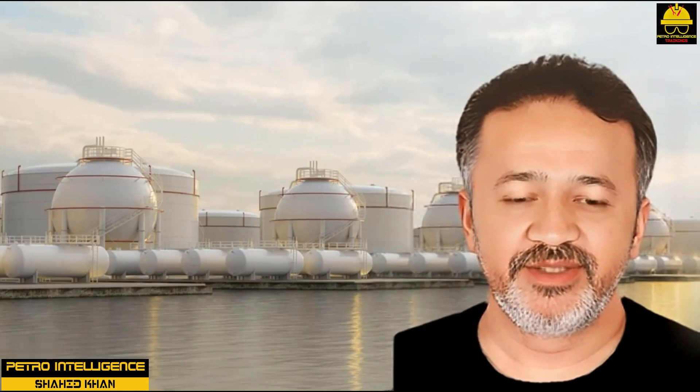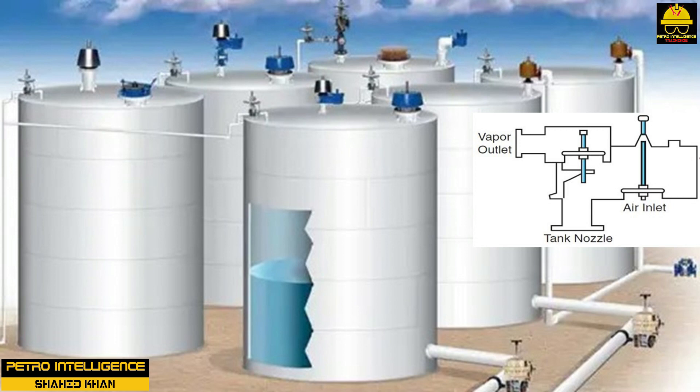Fixed-roof tanks that store volatile fluids are often equipped with a conservation vent. A typical conservation vent is equipped with two valves having weighted discs to regulate pressure during operation. The exhaust valve will not open until a slight positive pressure is reached in the tank, and the intake valve will not open until the tank is under a slight vacuum. Controlling the pressure in the tank reduces loss of vapors.